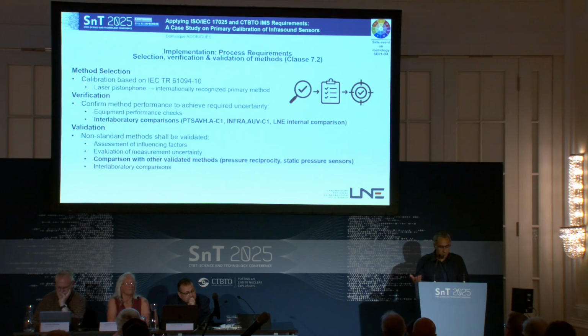So here also we have different tools to do that, but the strongest tool is probably a comparison, to provide comparisons of the results against other independent and recognized methods. So here we performed comparisons with other methods like the calibration of microphones by using a pressure reciprocity method, but also comparisons against a static pressure sensor, compared to a comparison provided by a static pressure laboratory.